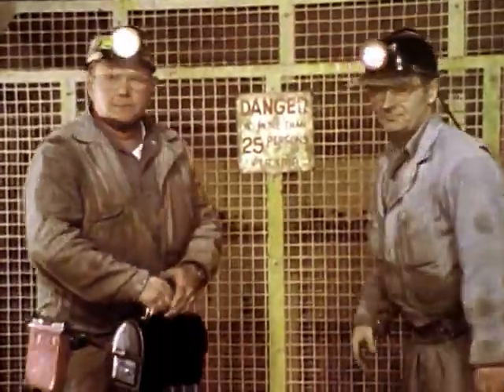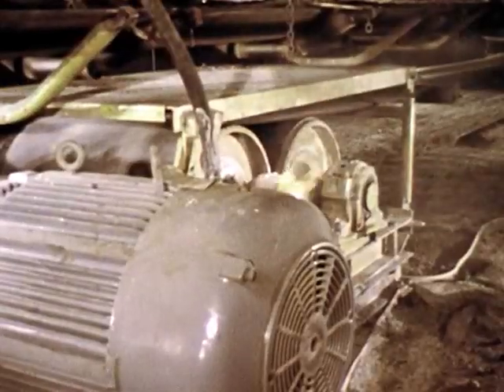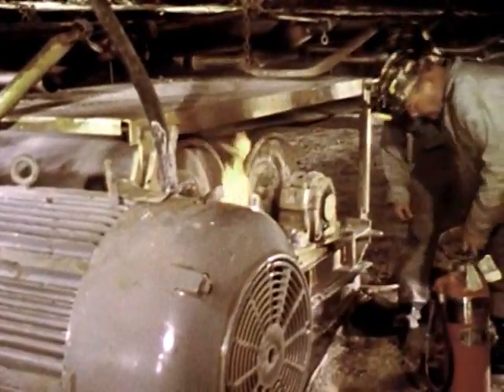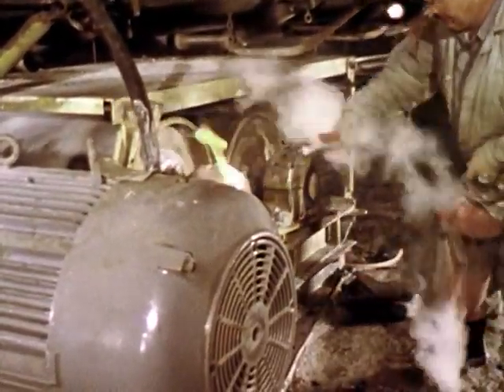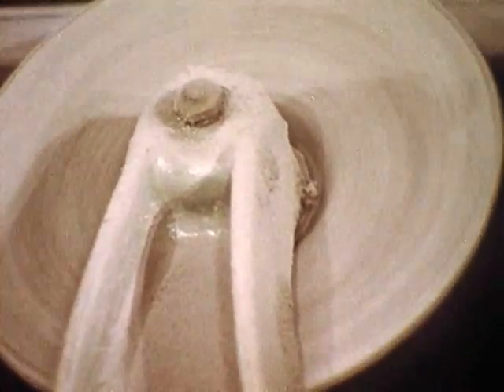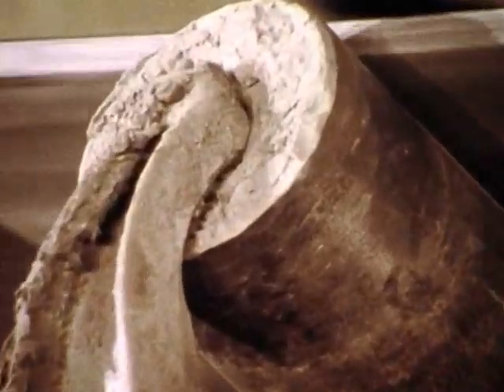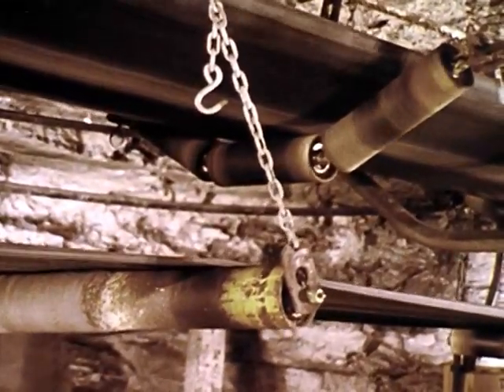To combat conveyor belt fires, workmen should be trained in firefighting and the use of proper fire extinguishers. Fire extinguishers should be maintained in good working condition and should be available at convenient locations. Frictional heat is also caused by belt slippage due to faulty belt tension, foreign particles, and overloading the belt. Frictional heat developed at the drive pulleys, tail pulleys, and at frozen trough or return idlers is often caused by worn-out bearings or lack of lubrication.